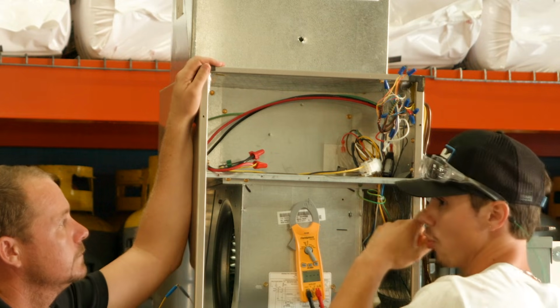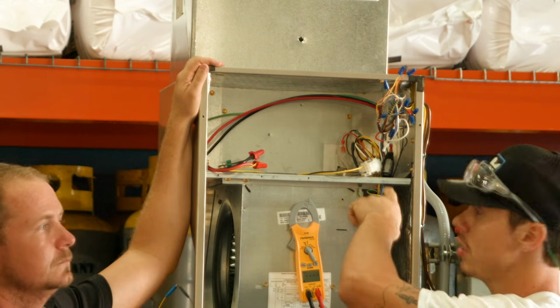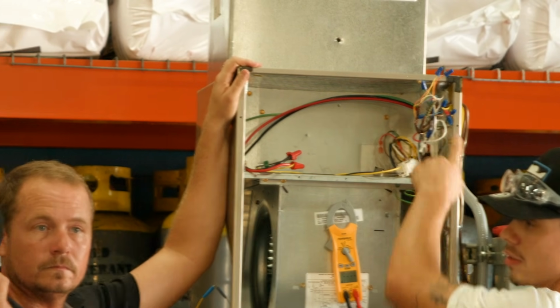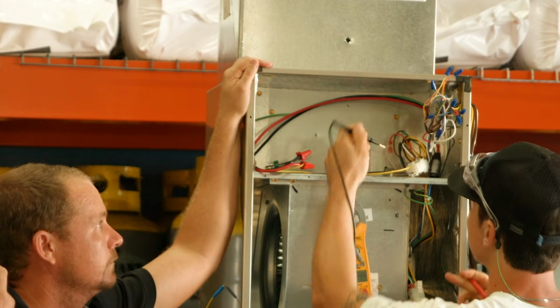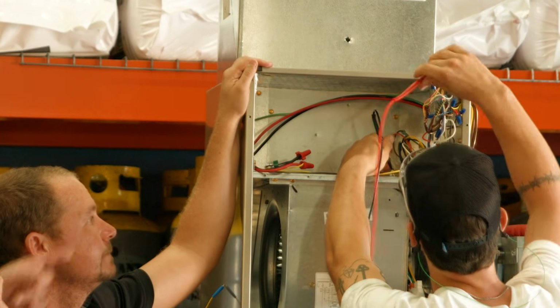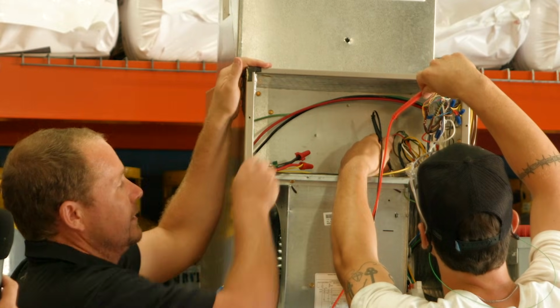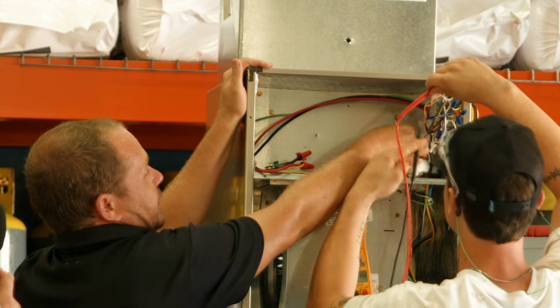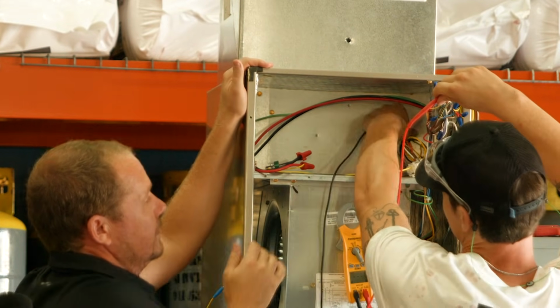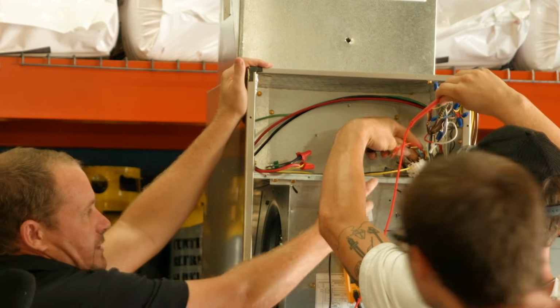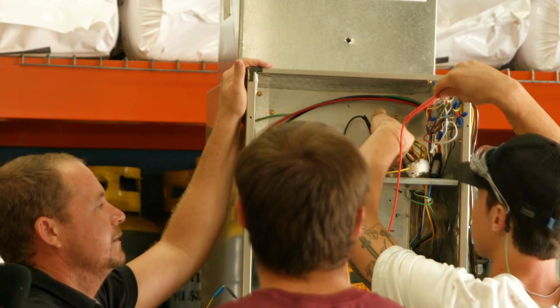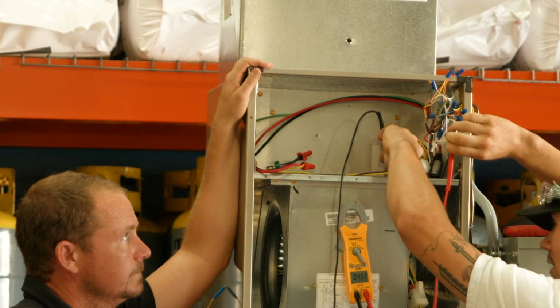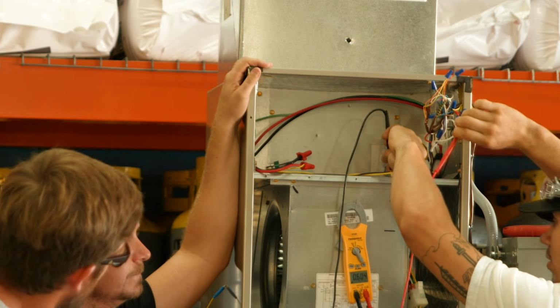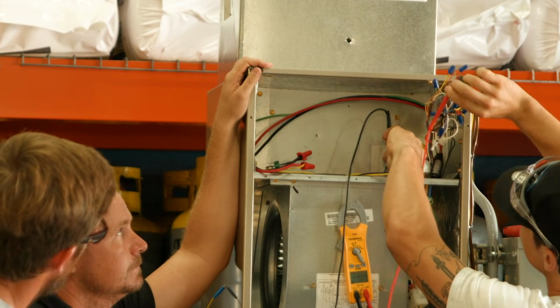And then your way, am I checking from common? I would check every wire nut to ground first, because your common's still bonded to ground the way that spade terminal is on that transformer. Yeah, if you see what he's saying here, your ground and your common are still connected together. So you don't even have to, just touch one lead to ground at that point. We're getting potential there. What are you getting as far as ohms? 14. I wouldn't be worried about that.